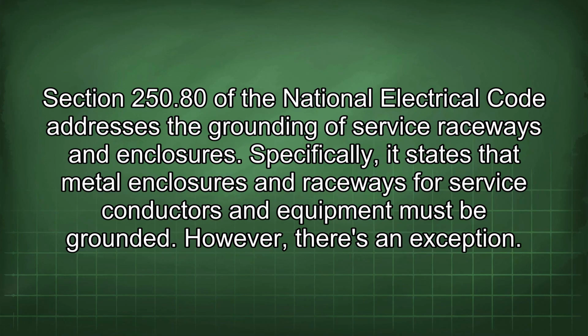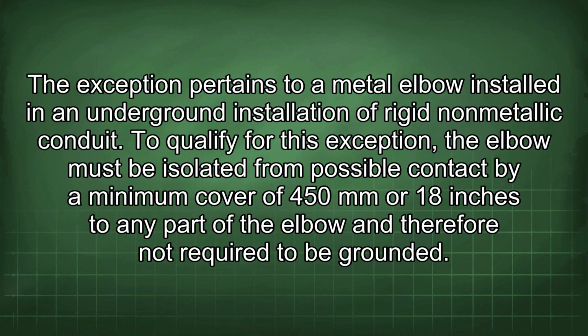Section 250.80 of the National Electrical Code addresses the grounding of service raceways and enclosures. Specifically, it states that metal enclosures and raceways for service conductors and equipment must be grounded. However, there's an exception. The exception pertains to a metal elbow installed in an underground installation of rigid non-metallic conduit. To qualify for this exception, the elbow must be isolated from possible contact by a minimum cover of 450 mm or 18 inches to any part of the elbow and therefore not required to be grounded.